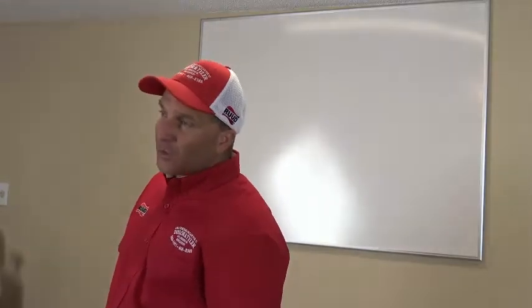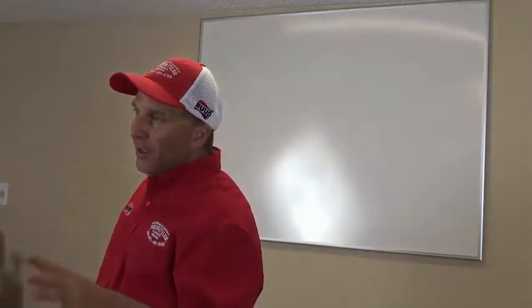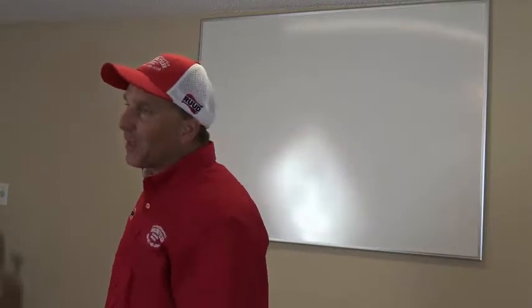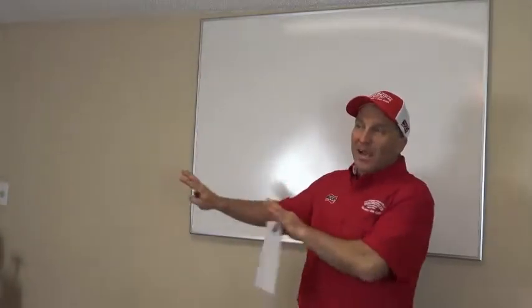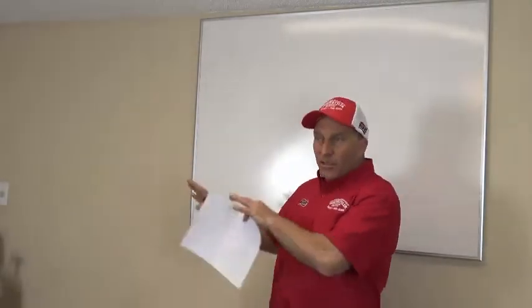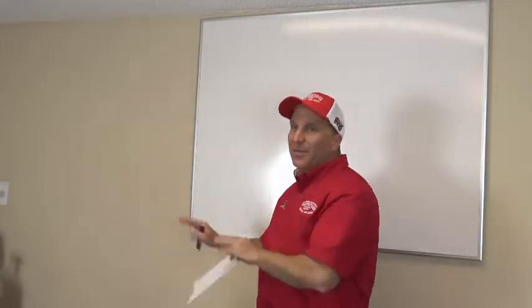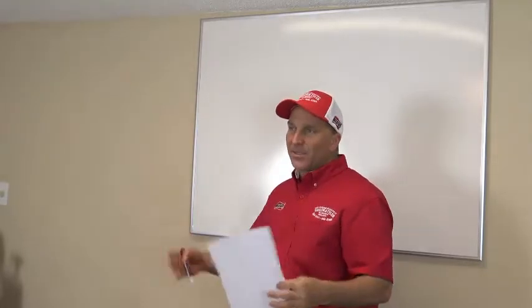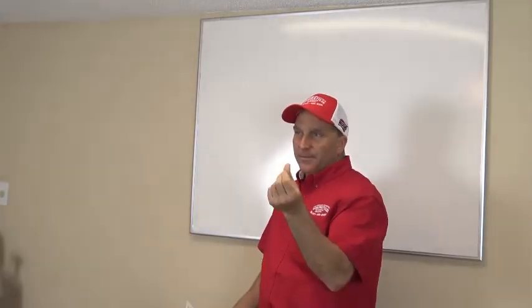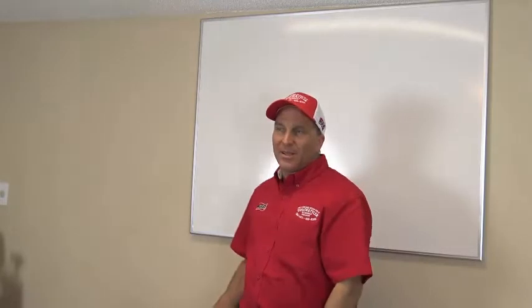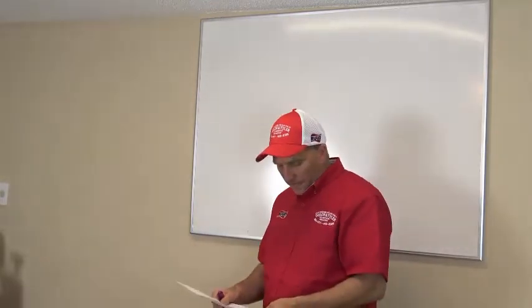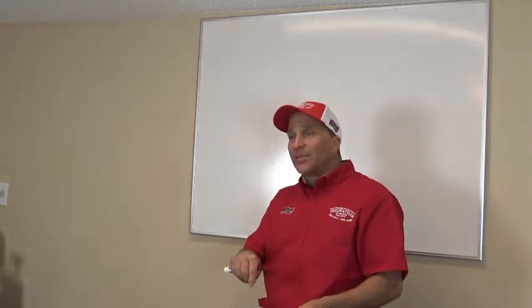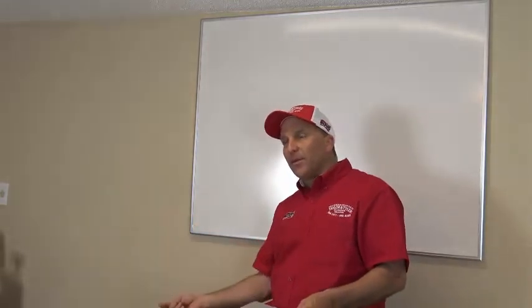All the new systems with variable speed and two-stage, with a circuit board there, it's got a time delay built into it. Okay? All the good systems have a time delay. All the old systems, the good systems from years ago, had a time delay. Today, they don't come with time delays. You know why? Costs a little bit less. That's the reason. Okay? Plus, they have scroll compressors today comparative to the old reciprocating compressors.